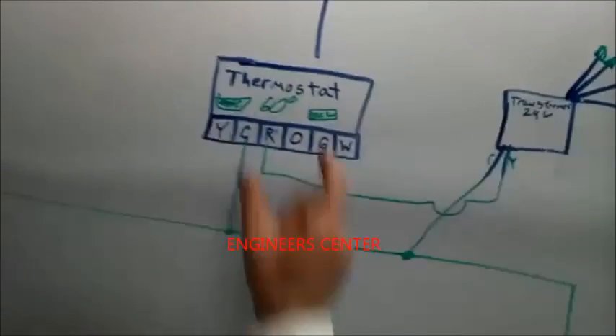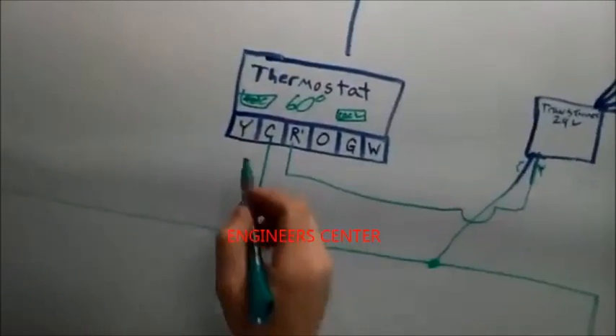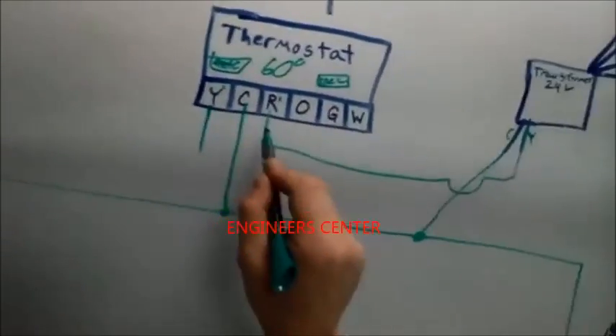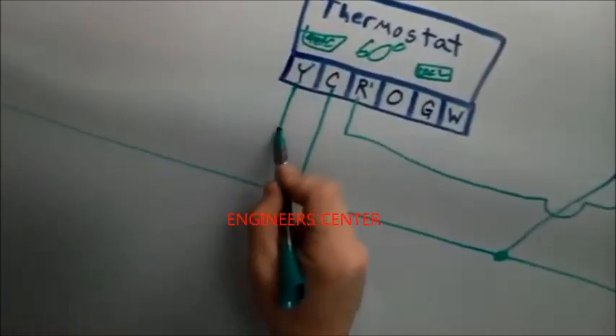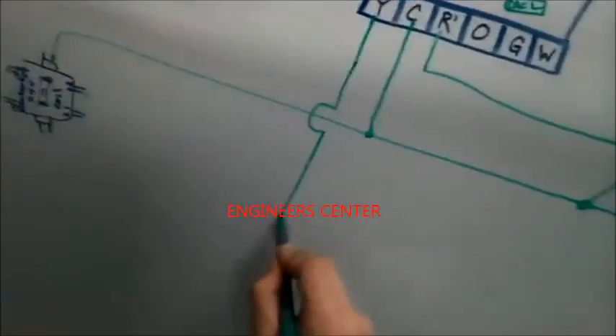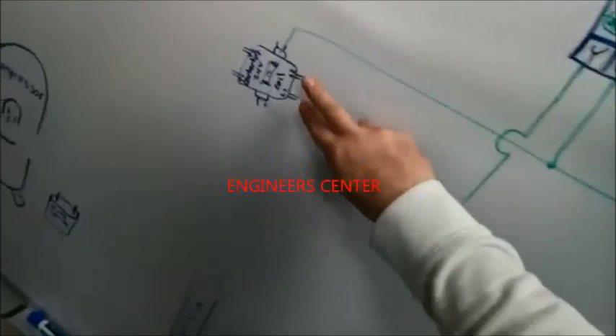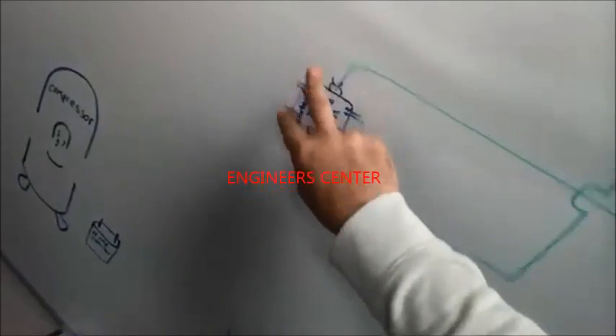When we put it in demand, it closes red to yellow, and so now yellow is going to be continuing this other line of 24 down, and it's going to go to your contactor, which would now close your contactor. So if you had high volt coming in, you would now energize high volt to your parts.